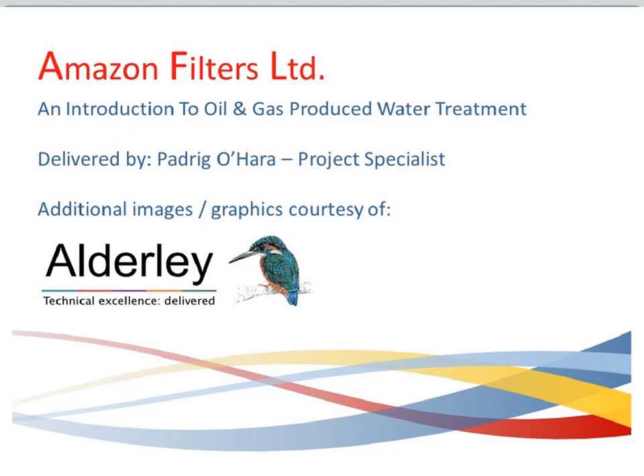One consideration is future tie-ins. These days we're seeing offshore a lot of individually marginal or non-viable fields being discovered and tied back into, say, a floating installation or a platform. So when designing these facilities, we may want to keep future flexibility under consideration: if future water injection is required, are we going to have the flexibility to handle that? The challenge, particularly offshore, is that there's very little additional space or weight allowance typically on platforms or floating installations. So the chances of being able to retrospectively install equipment can be very, very limited.